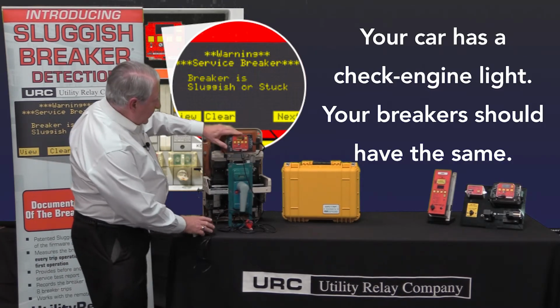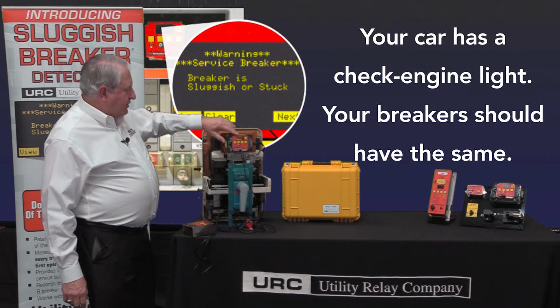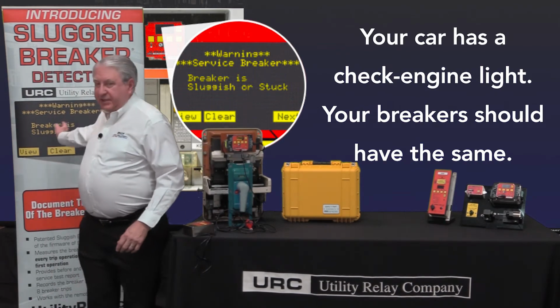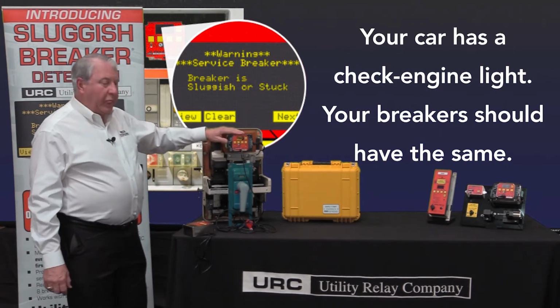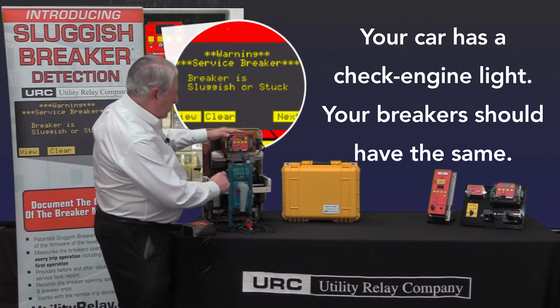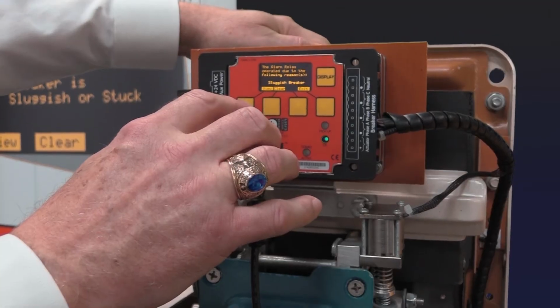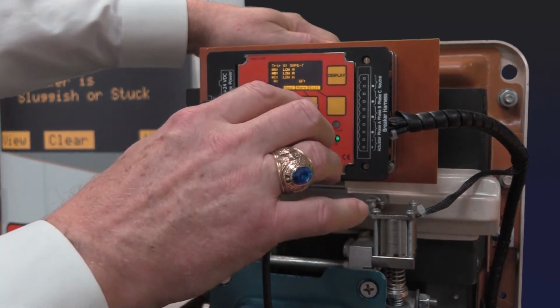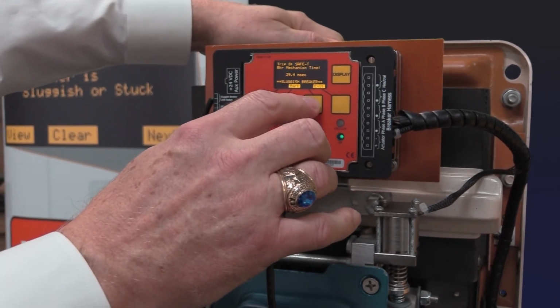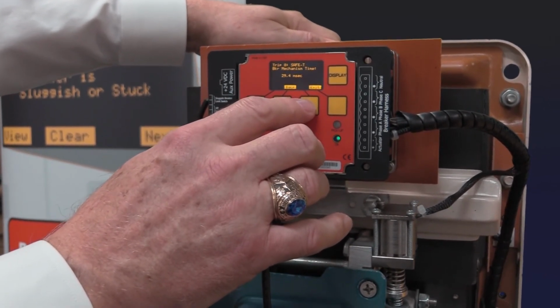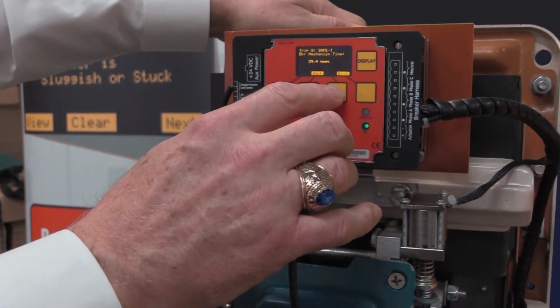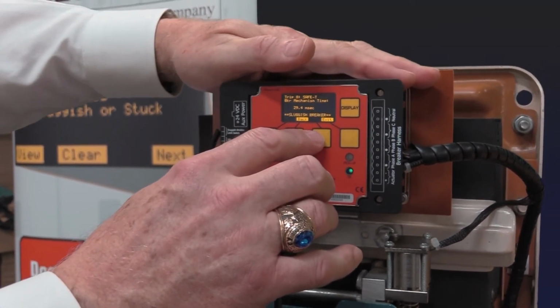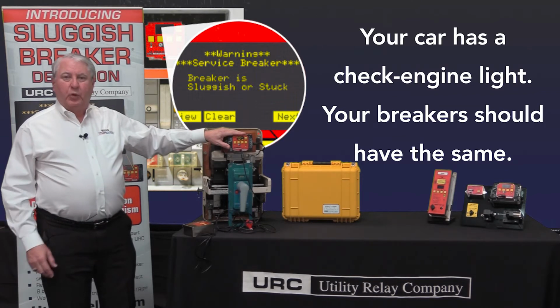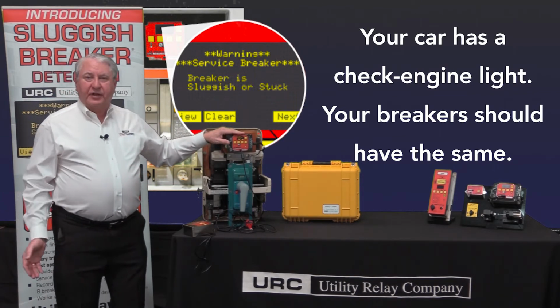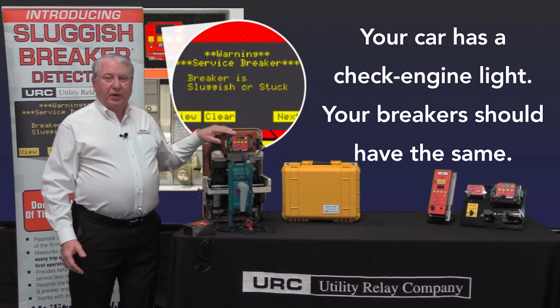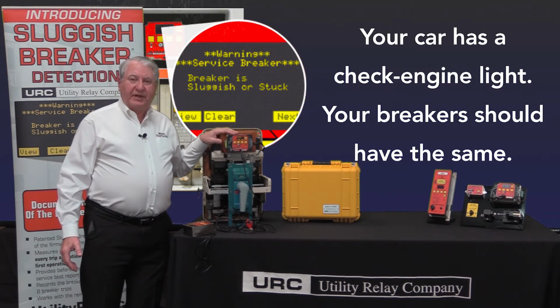And as you can see on the screen, it says sluggish breaker, just like it's shown on the banner here. And in this case, to review that information, I'm going to look at the information on the screen, and it shows that that trip took 29.4 milliseconds. Once again, in this case, longer than the 27 milliseconds built into this and programmed into this trip unit.